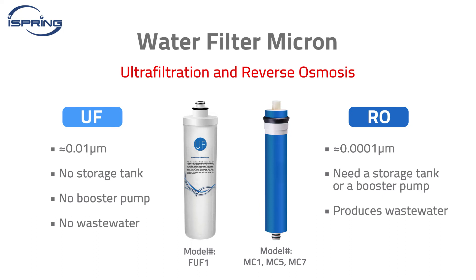A reverse osmosis membrane can filter the water down to near 0.0001 or 1 ten-thousandth of a micron. Since the pore size of the RO membrane is tiny, higher pressure is needed to push the water through the membrane. Therefore, a boost pump or a water storage tank may be necessary if the water pressure is low.